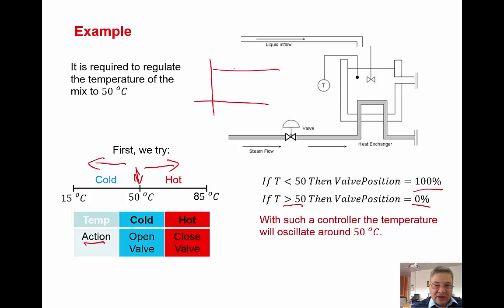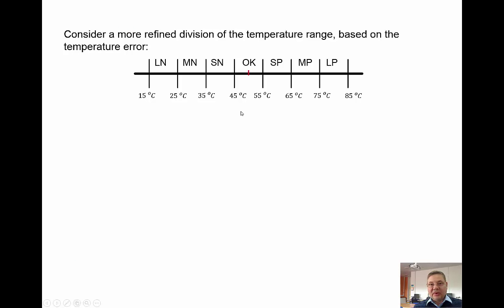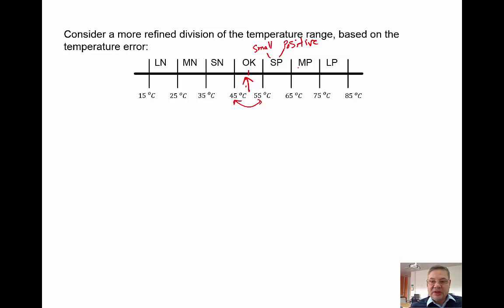With such a controller, the temperature will oscillate around 50 degrees. To get rid of the oscillation, rather than just cold and hot, I divide the range further. I define an okay region around 50 degrees — say between 45 and 55 — and then small positive, medium positive, and large positive on the high side, and similarly small negative, medium negative, and large negative if the temperature falls below the desired value.